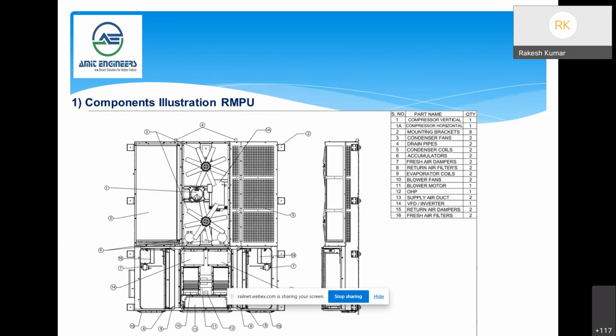Sir, actually, we want to have a modulated capacity, and only variable speed can give a modulating capacity. At present, a rail suitable vertical compressor is not available. That is why we have gone to a horizontal compressor. Otherwise, in other commercial applications, vertical variable frequency compressors are available. Whereas for a transport application, only the horizontal compressor is available as on date. The vertical variable speed compressor is under development. Okay, right. So we hope very soon we'll be getting that. Once we get that, we also wish to have a similar one.